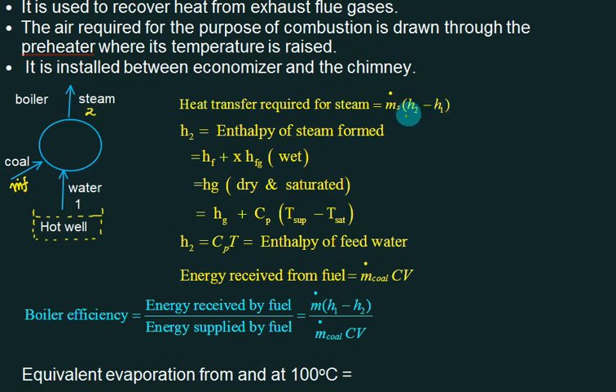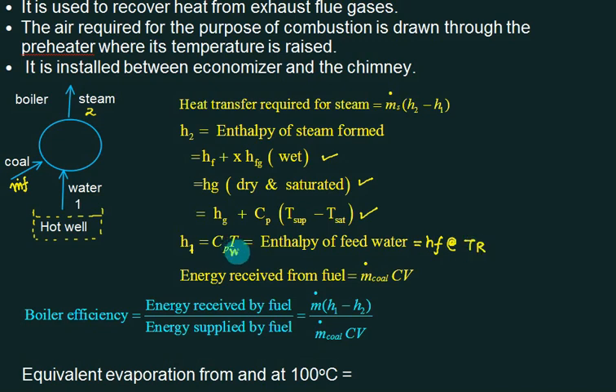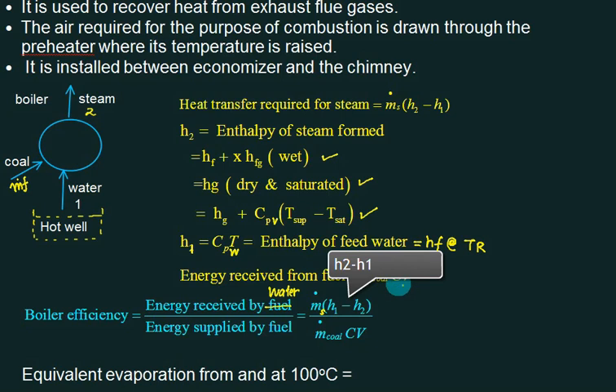H2 you can calculate as wet, dry saturated, or superheated. H1 equals either HF at room temperature or you can calculate using CP of water (4.2) and CP of vapor (2.1). Boiler efficiency is defined as the amount of energy received by the water divided by the amount of energy supplied by the fuel: [m_s × (H2 − H1)] / [m_f × Calorific Value].